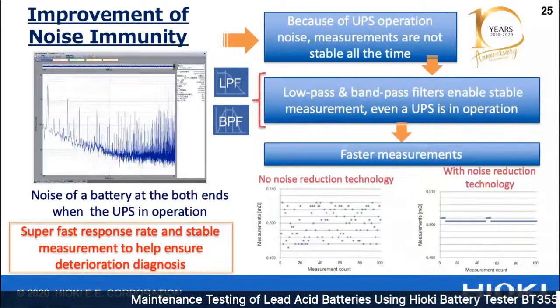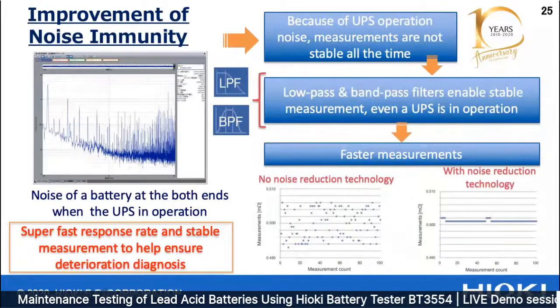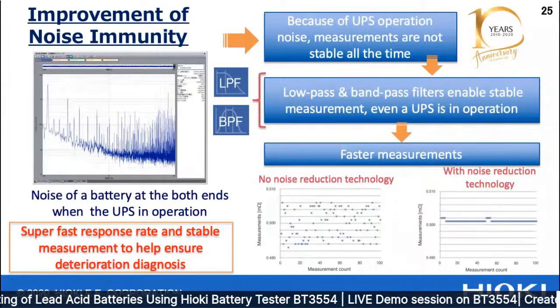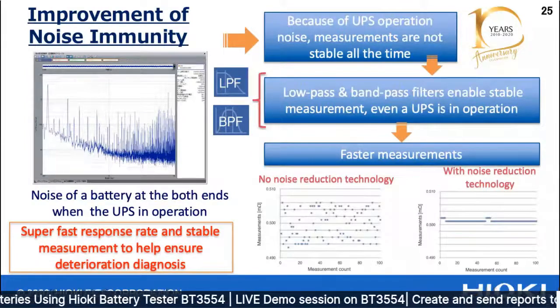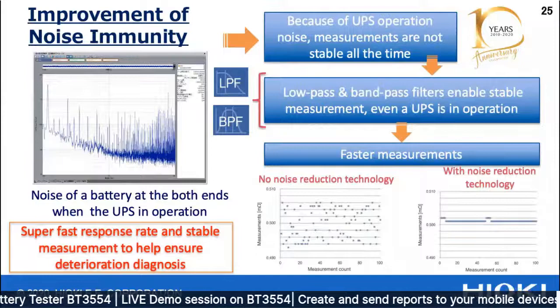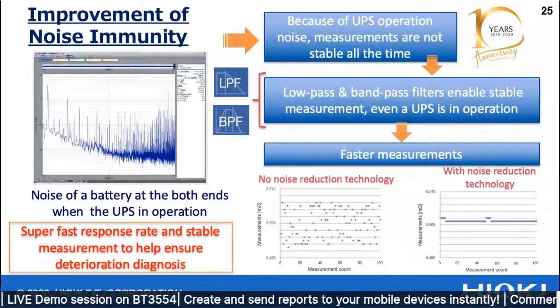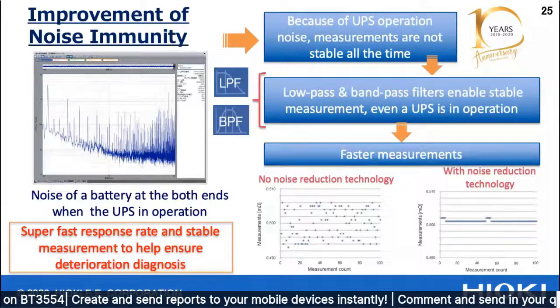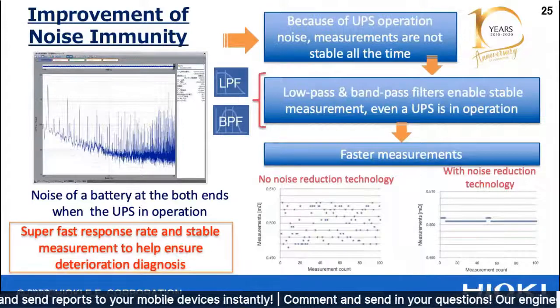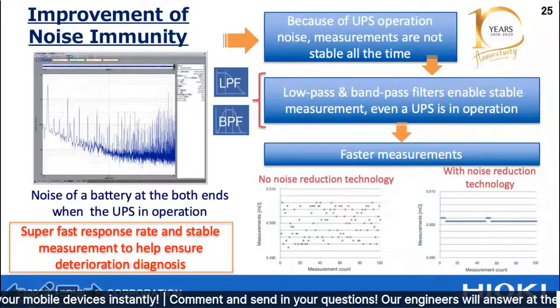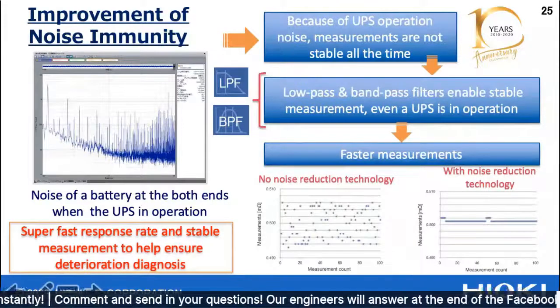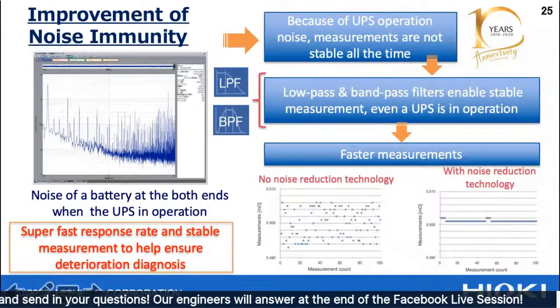First, for a UPS that is in operation, the noise level is quite high, even more so when there is an electronic load where switching is involved. This makes the measurements unstable, so you get high and low readings that are not repeatable.